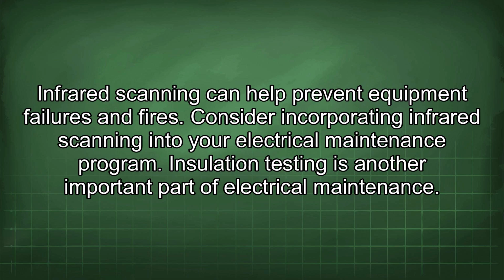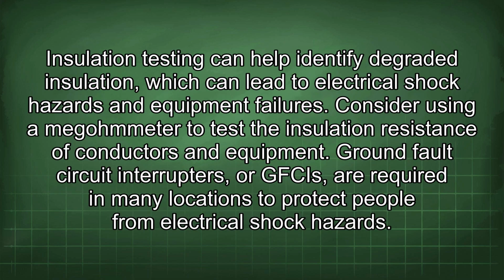Insulation testing is another important part of electrical maintenance. Insulation testing can help identify degraded insulation, which can lead to electrical shock hazards and equipment failures. Consider using a megohmmeter to test the insulation resistance of conductors and equipment.